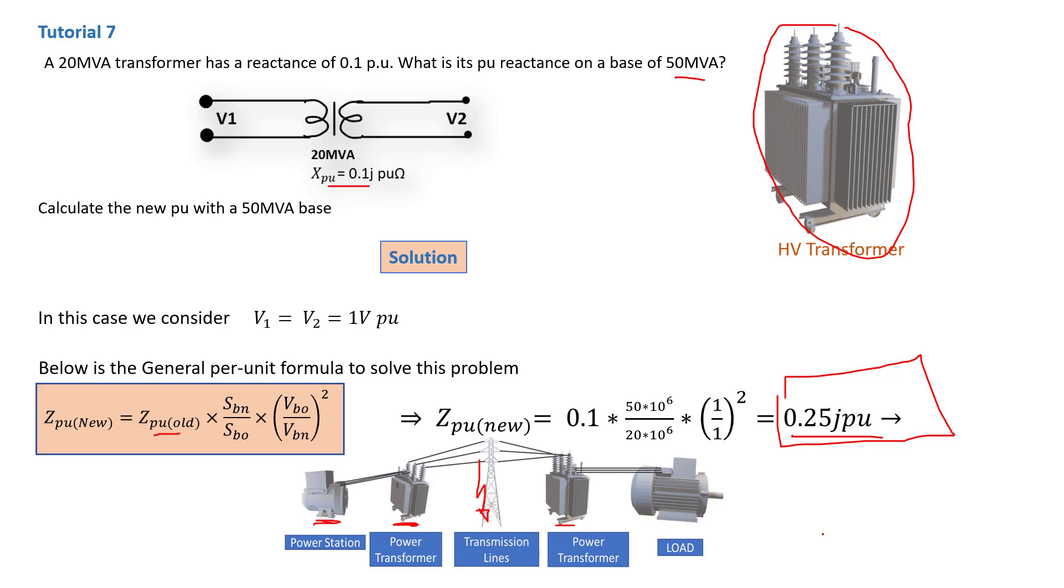So this is why it's very important doing power system analysis, knowing how to do your per unit calculations. Ultimately, that's going to help you if you want to ensure your system is protected. Because based on the magnitude of the fault current, you'll be able to determine what is the protection required, the size of the circuit breaker or any other protection apparatus.